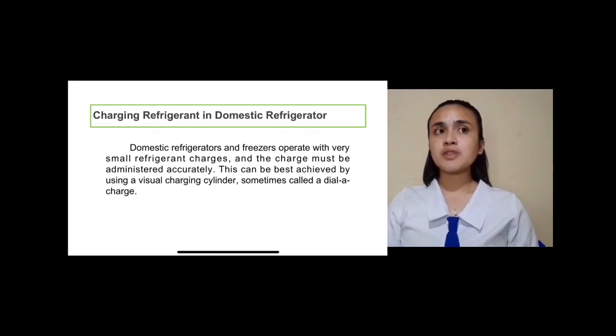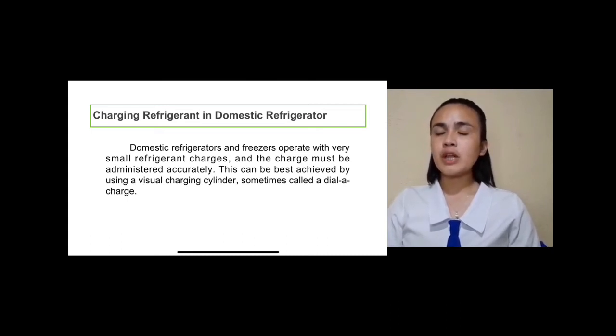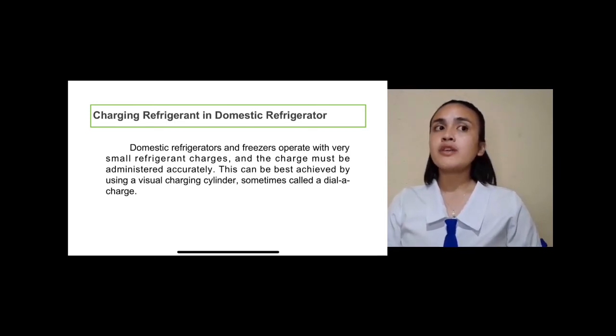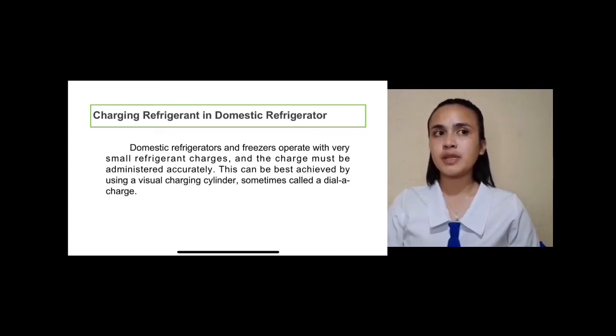Charging a refrigerant system is one of the most challenging and puzzling tasks a service technician will face. How much refrigerant a technician should put into a system when charging is a tough question to answer, because it is often system dependent. If there is no nameplate specifying the charge amount in ounces and pounds, there is really no straightforward answer, because all refrigeration systems differ in the amount of charge they hold. This is especially true for field assembled refrigeration systems in which suction line length and size can vary considerably.